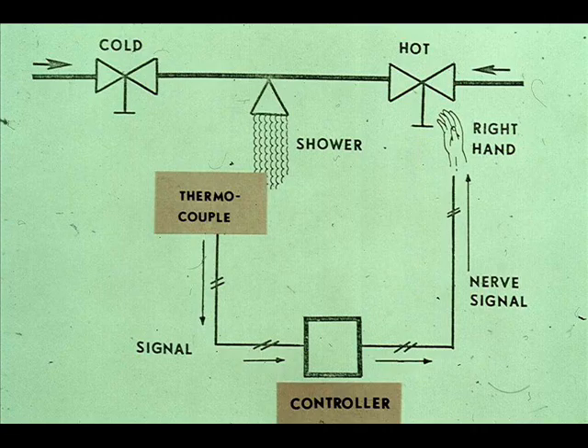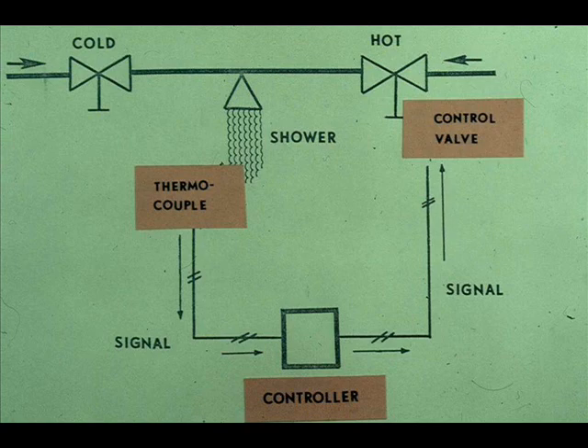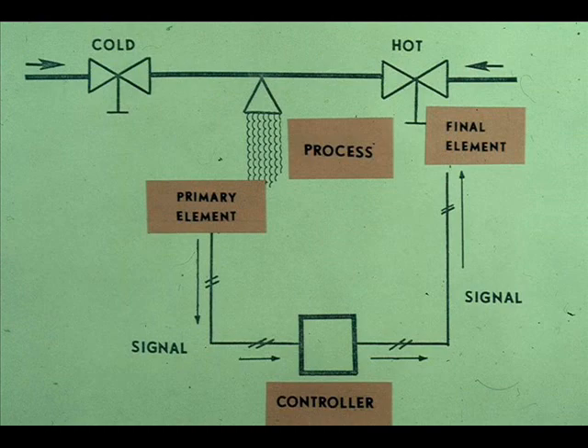Now suppose we wanted to automate the shower system. We replace the left hand with a thermocouple, which will sense the shower-water temperature. The thermocouple transmits this temperature to a controller, which has replaced the brain. The controller compares this actual temperature with the set point temperature, and then sends a signal to a control valve, which has replaced the right hand shower valve. The control valve then opens or closes to bring the water temperature to the set point or desired temperature. Now you have an automatic control loop that has all the essential elements: the process, primary element, controller, and final element.